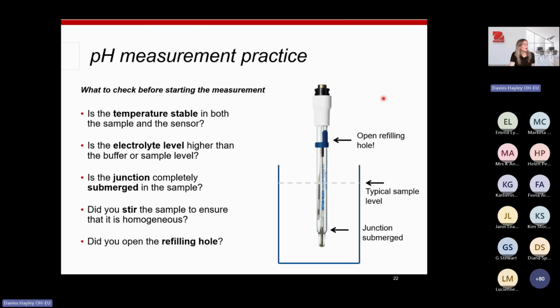Just double check when you are measuring the sample: is the temperature stable in the sample and the sensor? Is the electrolyte higher than the level of the buffer or sample level? This means that if your sample level is here, you need to make sure your electrolyte is higher than that sample level. Is the junction completely submerged in the sample? Did you stir the sample to make sure that it's all nice and homogeneous? And did you open the refilling hole? When you have a refilling hole, it's important to open it once it's in the sample, just to make sure that the electrolyte can flow out of the junction.